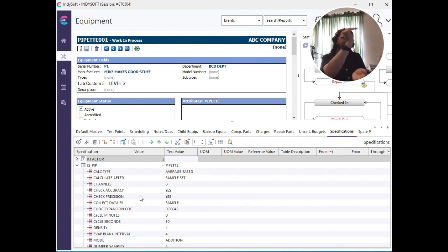As that information grows, if I'm working with attributes, that starts to become painful because you've got all of these different modules fighting on how they want to define a balance. With specifications, I can just make more nodes. This is the pipette node, this is the balance node, this is the weights node, and it gives us flexibility to have what we want where we want it.